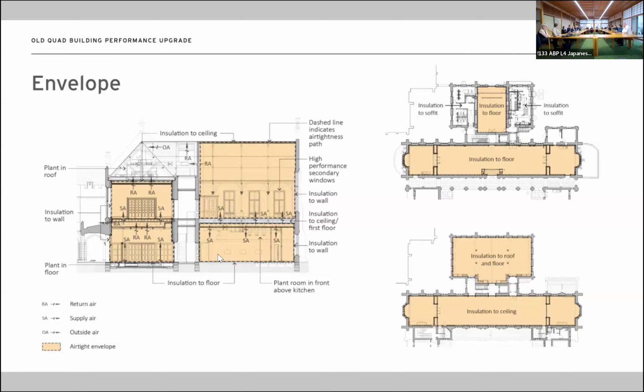So all the air distribution that comes through into the spaces, we have ducts hidden inside the walls to inject the air at low level. We call that displacement ventilation. And in some areas, we use that floor zone, which is called underfloor air distribution. So what that enables us to do is, instead of having to look at the entire air volume of that space, we can just look at the occupied portion of that space, the first 1.5 meters, 1.8 meters where everyone's sitting, and we just worry about climate controlling that component of the space. Because this space is so heavily insulated, what we're always thinking about is just injecting a small amount of cool air when those spaces are busy.